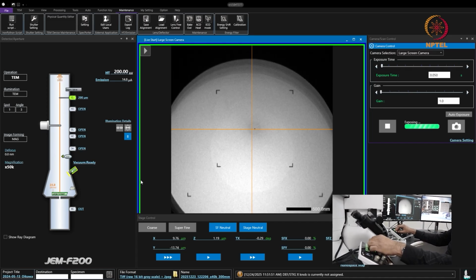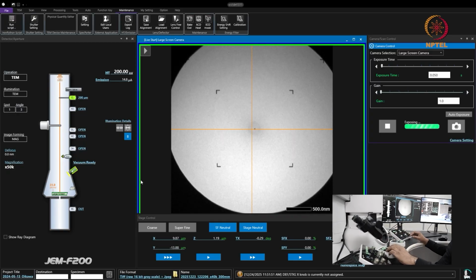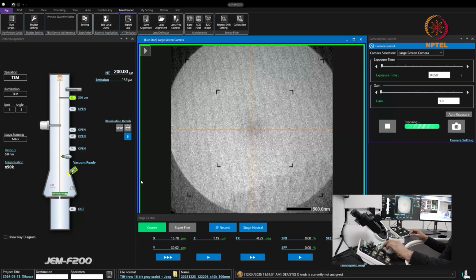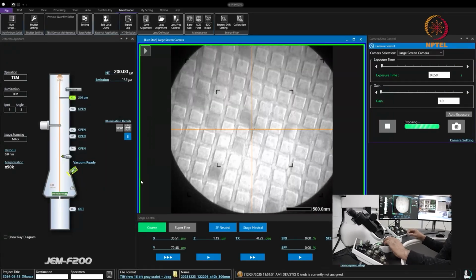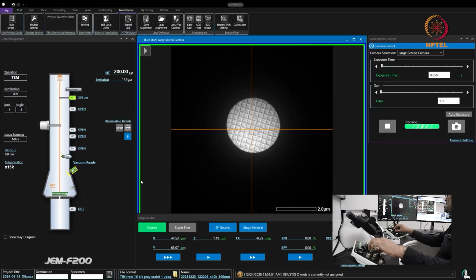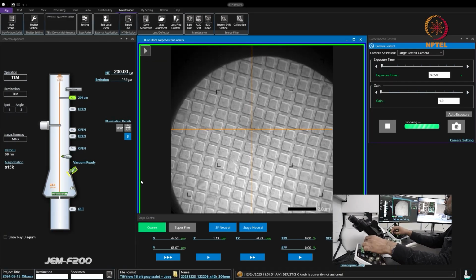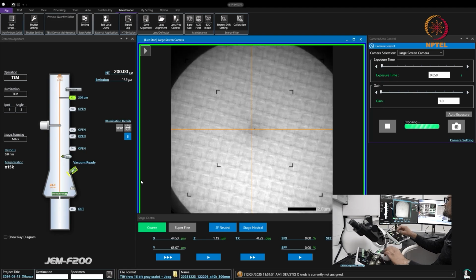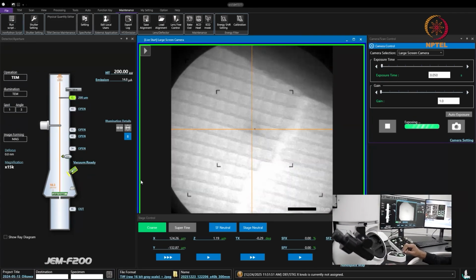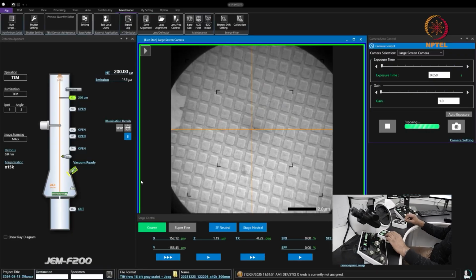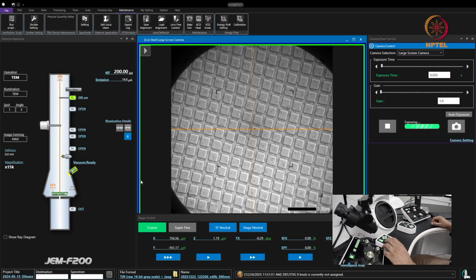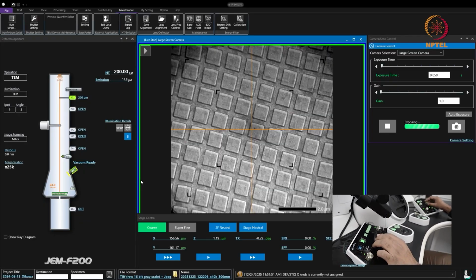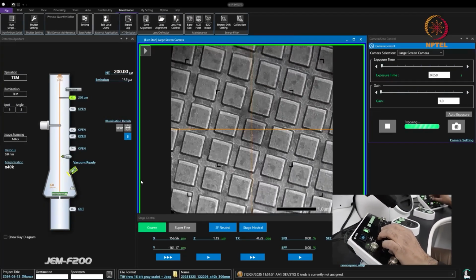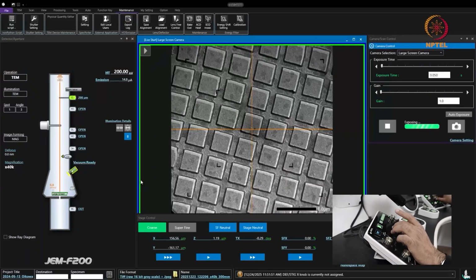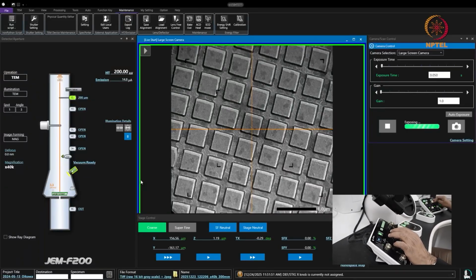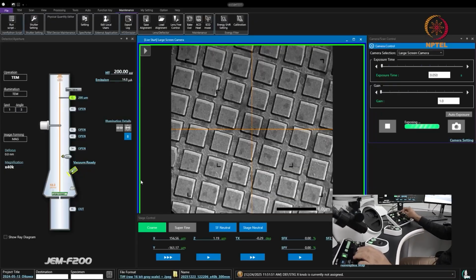to the right eccentric height. So for this, I go to the area of interest on my specimen, which is somewhat like this, and I go to a magnification of around 25 to 50,000x. The same way I corrected the eccentric height by using image wobbler in the other instrument, I do the same procedure here.